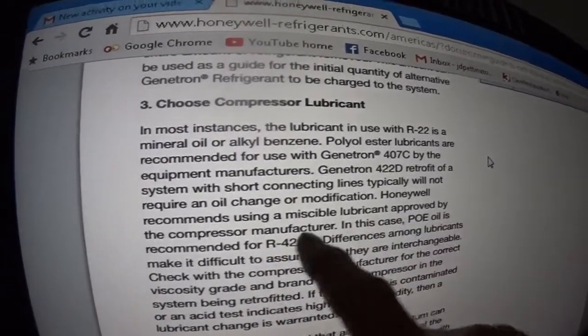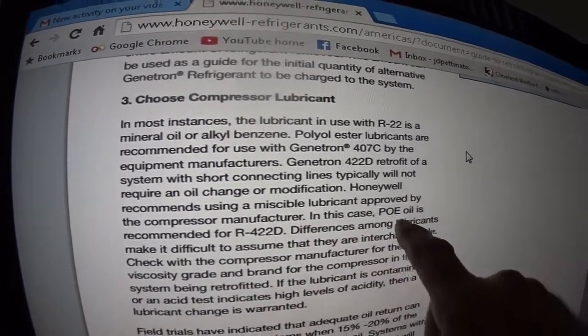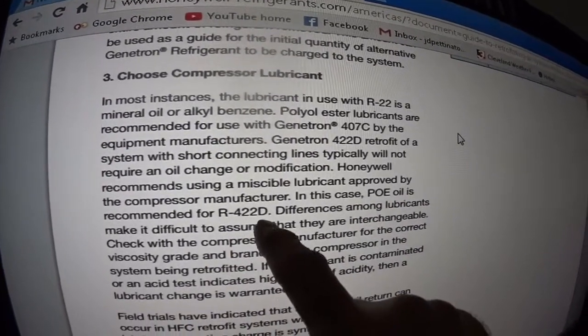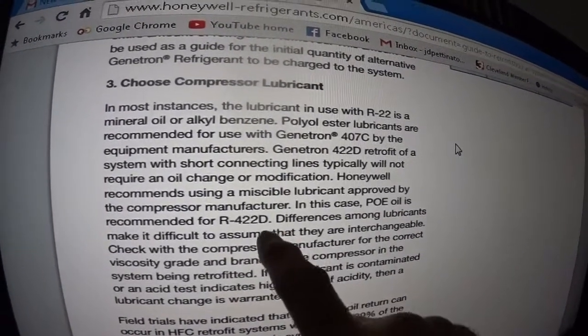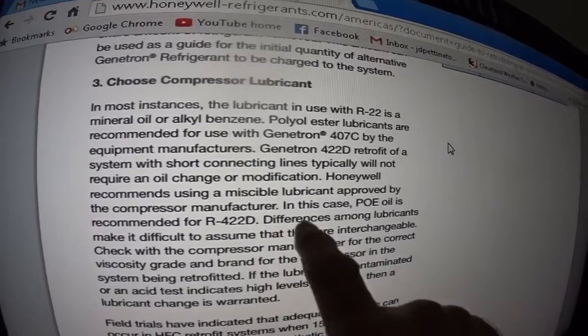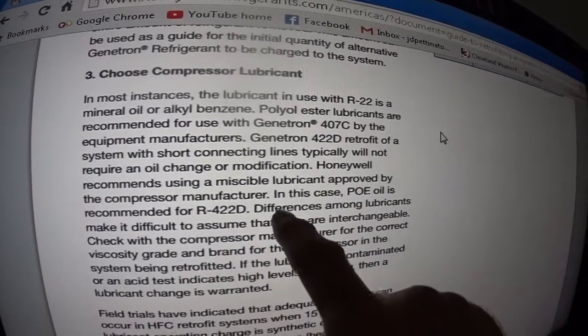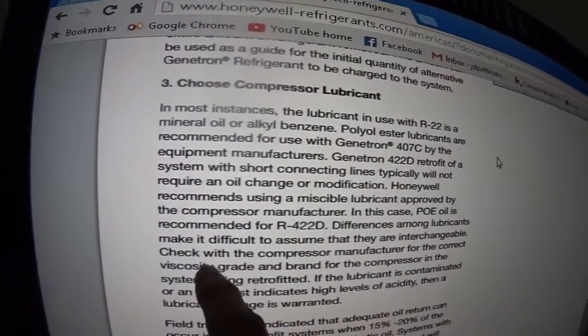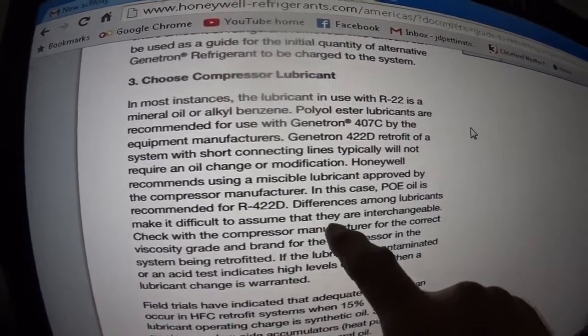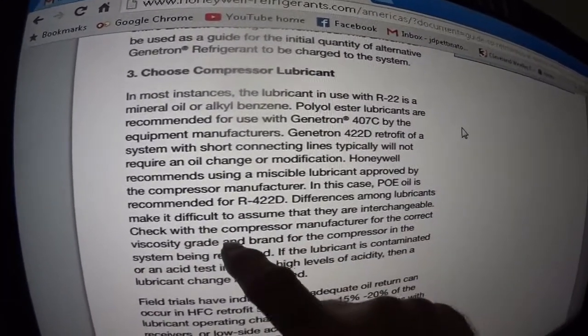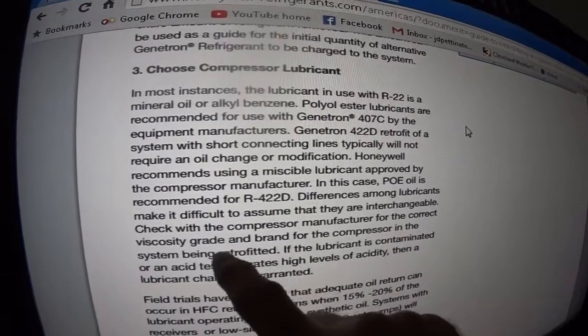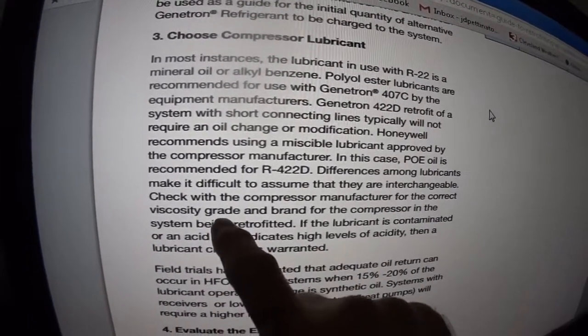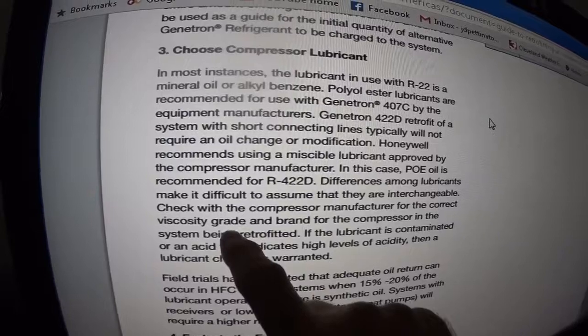Honeywell recommends using a miscible lubricant approved by the compressor manufacturer. In the case of 422D, POE is recommended. Differences among lubricants make it difficult to assume they are interchangeable — check with the compressor manufacturer for the correct viscosity.